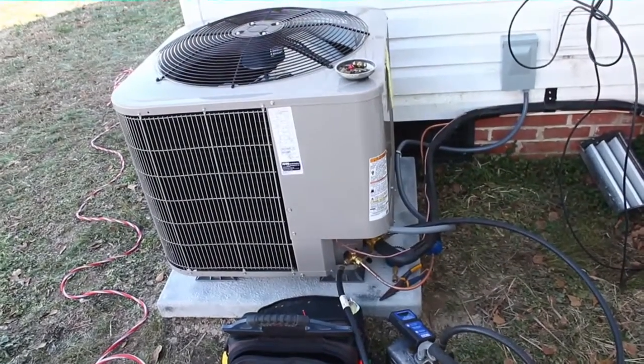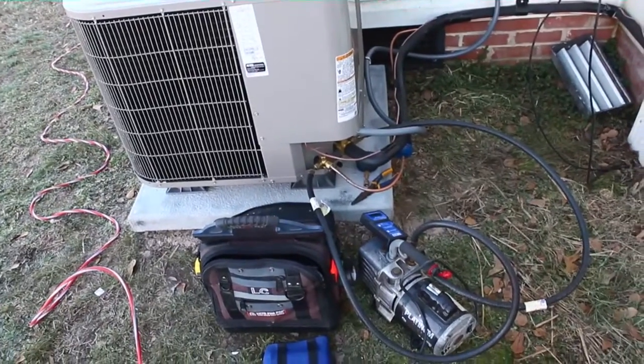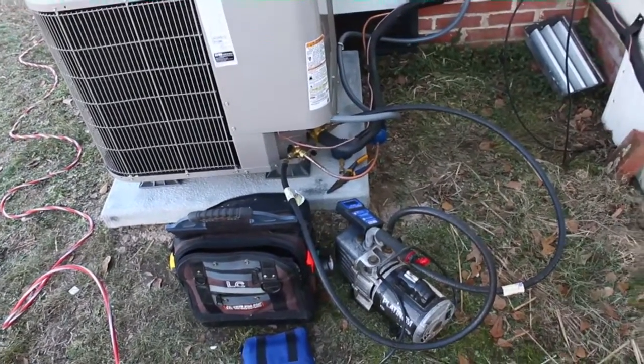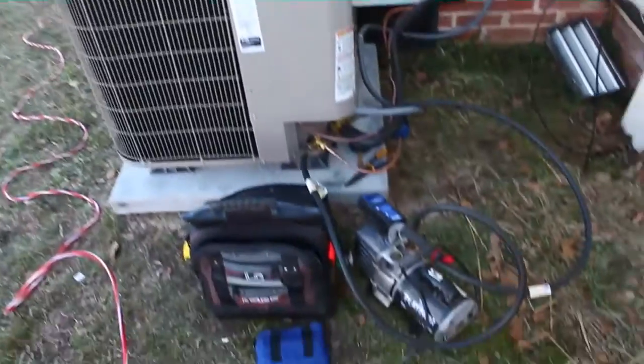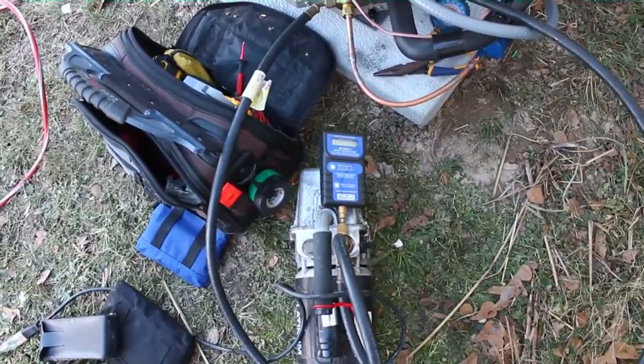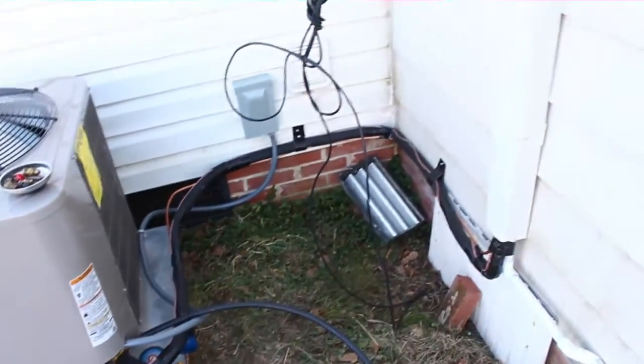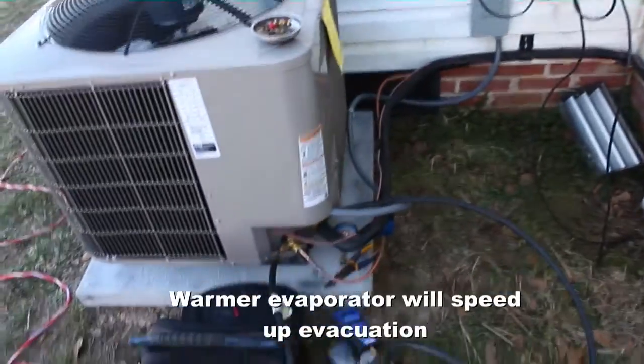We are back on the job Saturday morning here to start up the unit. Put the unit into vacuum. Wanted to make sure it held nitrogen overnight, which it did. It's going to take a while today. I don't know what temperature it is right now, but somewhere in the 30s. So it's going to take a little while to pull a vacuum. The air handler's on, emergency heat's running, so hopefully it warms up that evaporator coil a little bit.